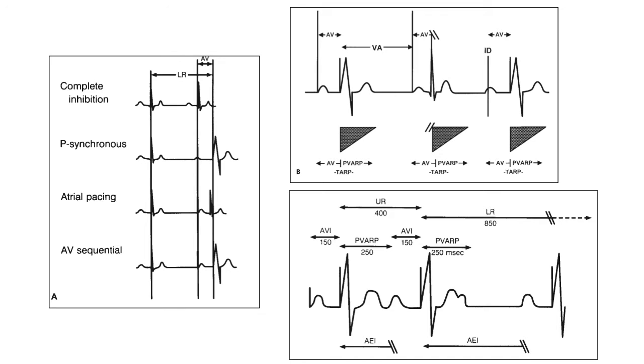In dual chamber systems, the sensed or paced atrial event will initiate both an atrial refractory period and the AV interval. During this part of the timing cycle, the atrial channel is refractory to any other native atrial event, and atrial pacing cannot occur during this period. The atrial pacing can occur only at the end of the AV interval or after that.